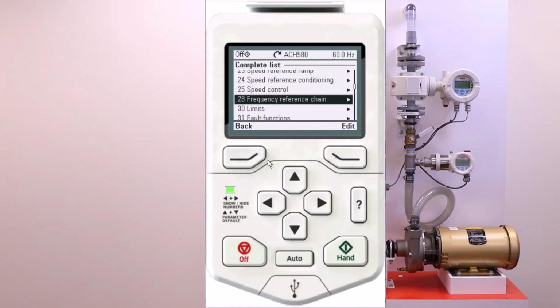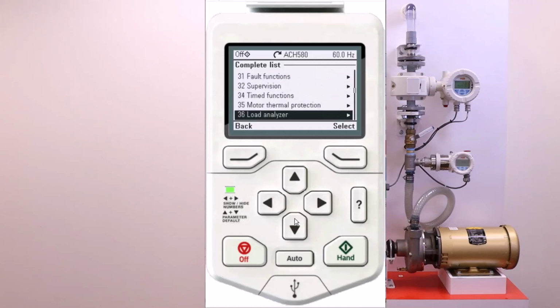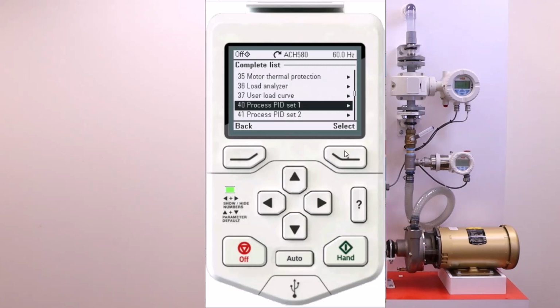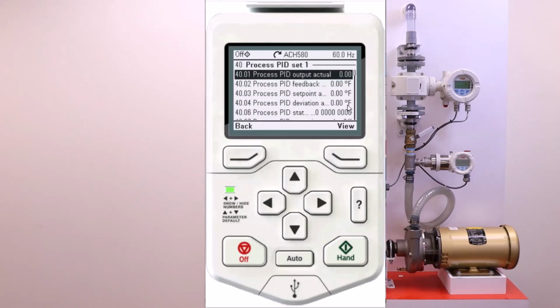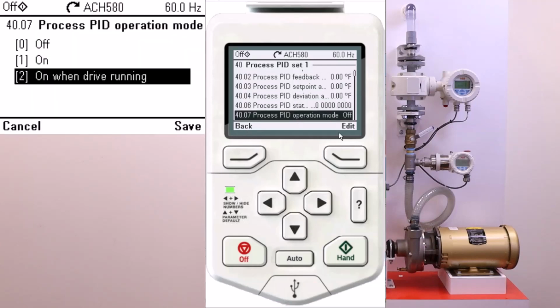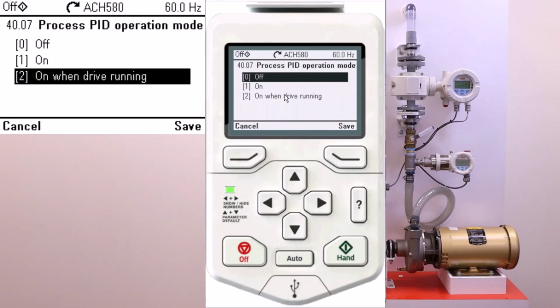We back up. Next thing we go to is group 40, because group 40 is our PID loop. There's your PID loop. Select. So let's start out with our PID loop in group 40. The first parameter we need to go to is going to be 4007. 07 is our operation mode, and currently it's off. So we're going to enter that. We want it to be on.